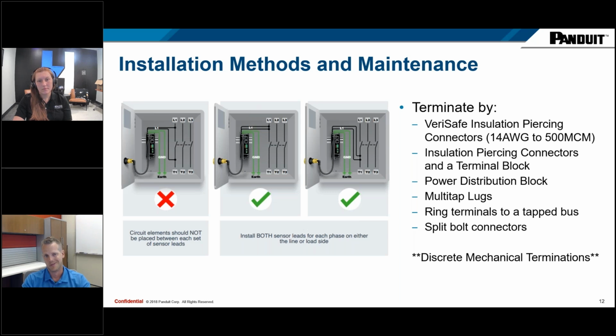You can terminate through our insulation piercing connectors that go anywhere from 14 American wire gauge to 500 MCM. If you use other insulation piercing connectors, you can integrate those with a terminal block. PDBs and power distribution blocks, multi-tap lugs, ring terminals if you're going to tap a bus, and then everyone's favorite, I'm sure, split bolt connectors, but you see those less and less now.